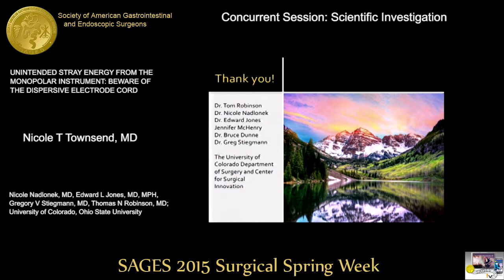That's a great question, and honestly, we've not explored increasing the amount of insulation on the cord. All of the cord insulation is intact. But what we've recommended is that even the simplicity of just isolating the generator on the other side of the patient is a way to reduce that clutter of all the cords going everywhere, and just keeping the two pathways of cords, the generator on one side and the cords on the other. But we've not explored increased insulation on the cords themselves to see if it will reduce stray energy transfer. Good. Yes. One more follow-up question.